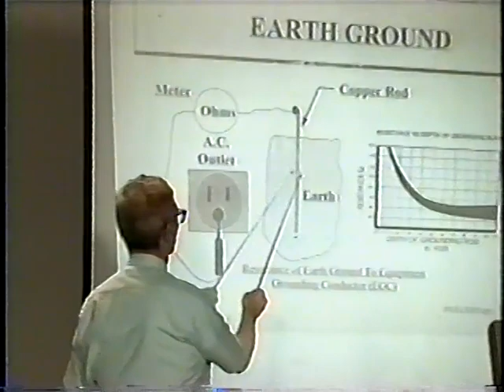Many people believe that you need an earth ground at every station. That is not necessary. A grounding rod has resistance, as you see from this chart - it is not 0 ohms to ground. The grounding resistance depends on the length of the rod, moisture, and other factors.